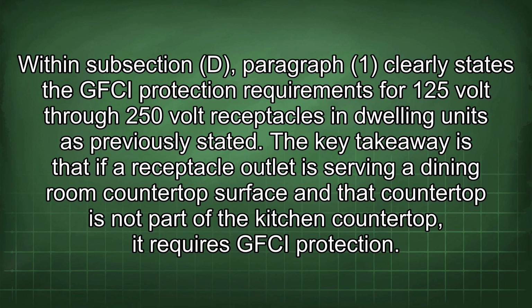Within subsection D, paragraph 1 clearly states the GFCI protection requirements for 125 volt through 250 volt receptacles in dwelling units as previously stated. The key takeaway is that if a receptacle outlet is serving a dining room countertop surface and that countertop is not part of the kitchen countertop, it requires GFCI protection.